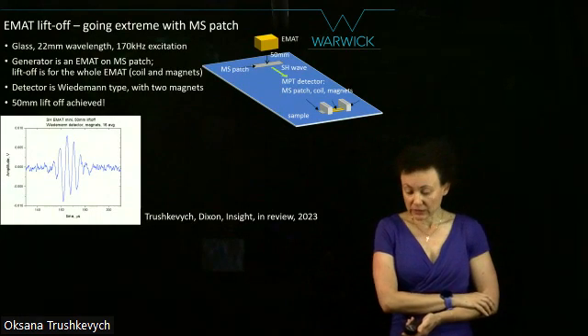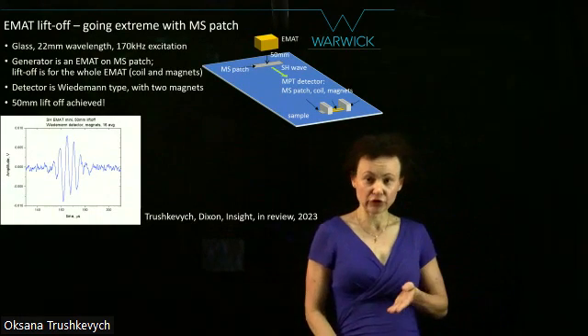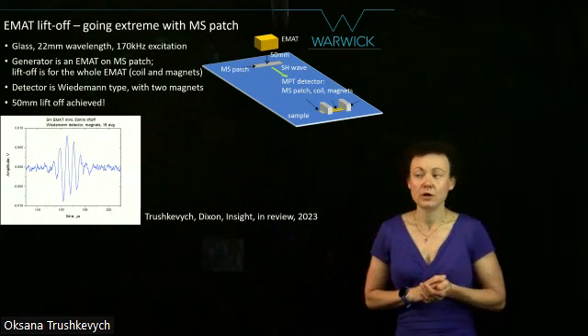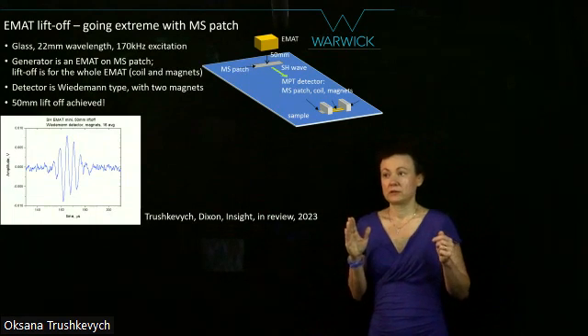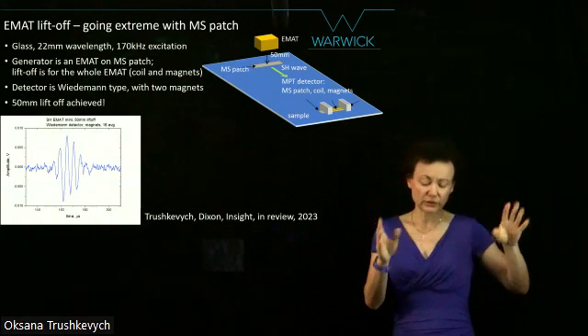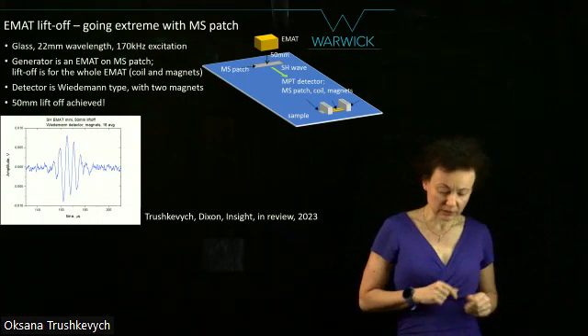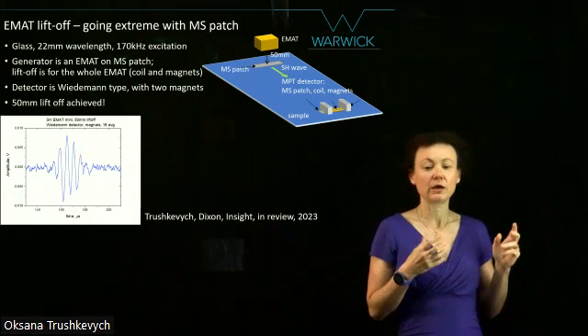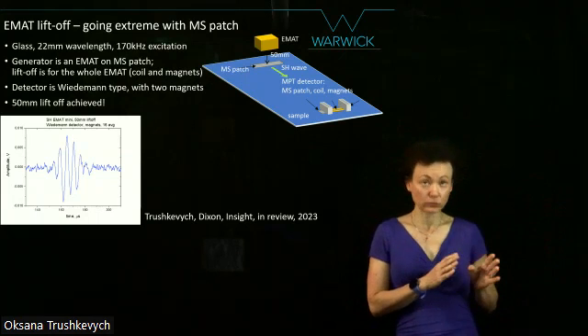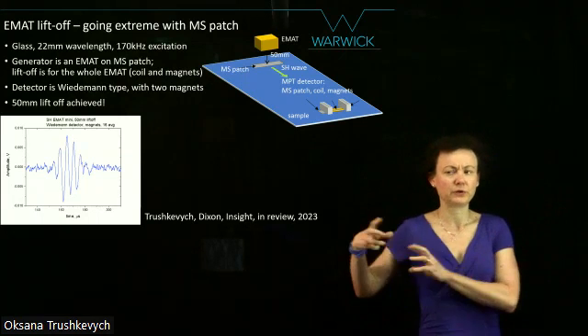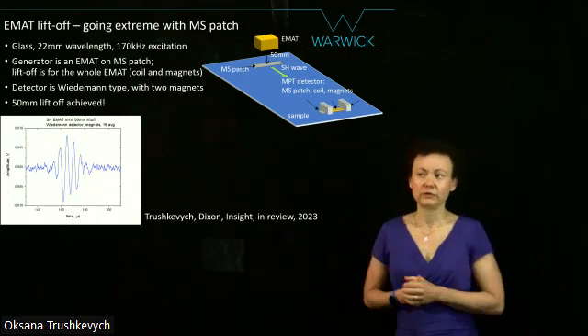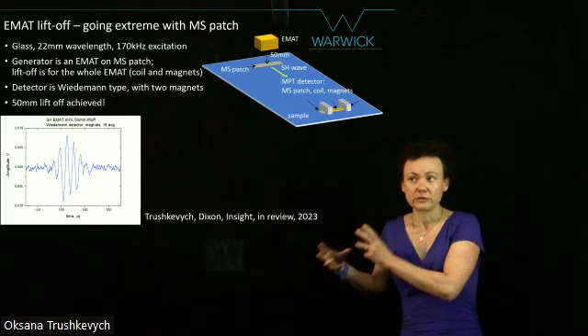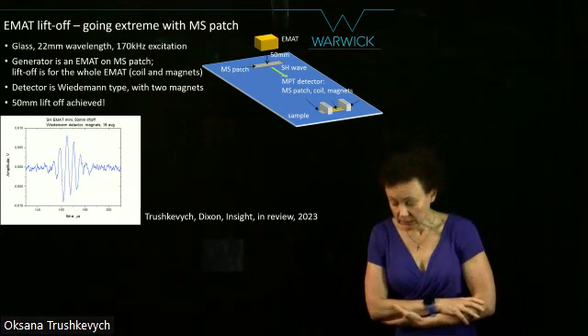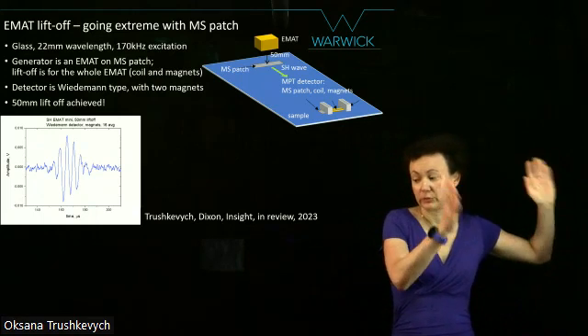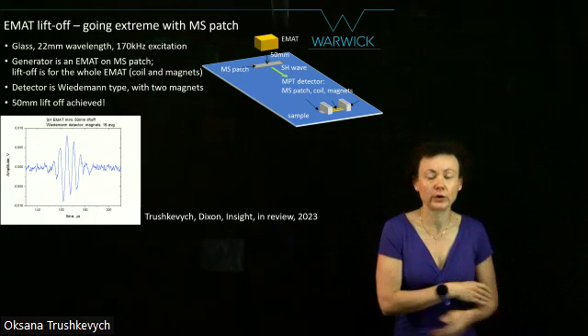The last bit on magnetostriction I wanted to share is that magnetostrictive patch transducers are distinct from EMATs - they have different geometry. They rely on magnetic fields only, not on currents, while EMATs rely on both currents and magnetic fields. EMATs require the sample to be conductive, while magnetostrictive patch transducers can be put onto anything and work.